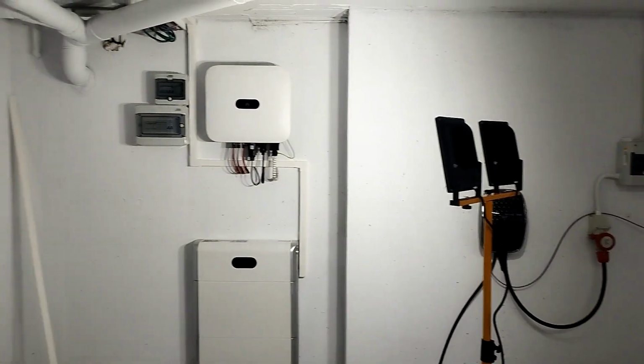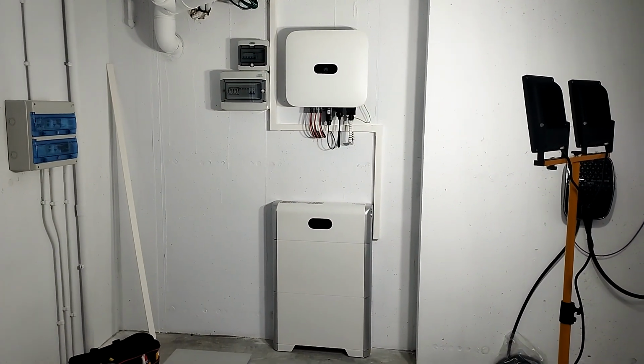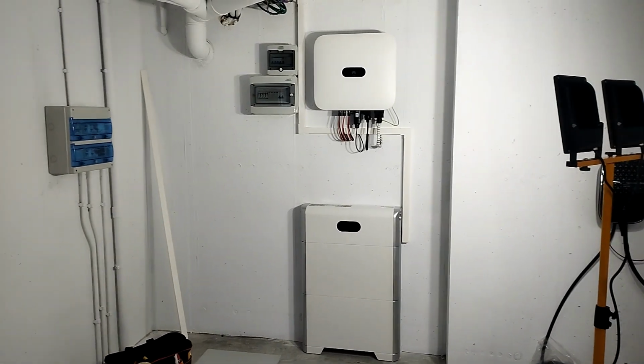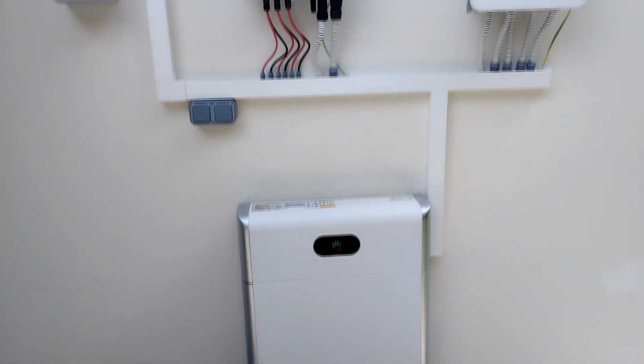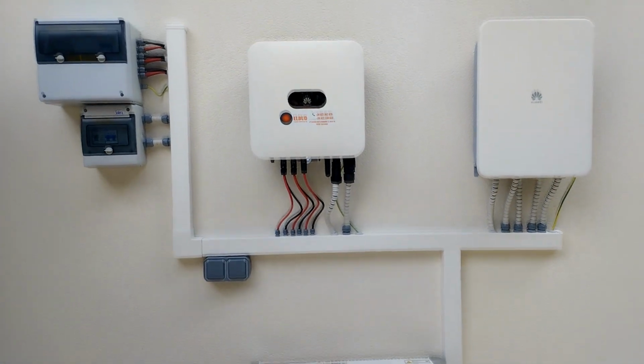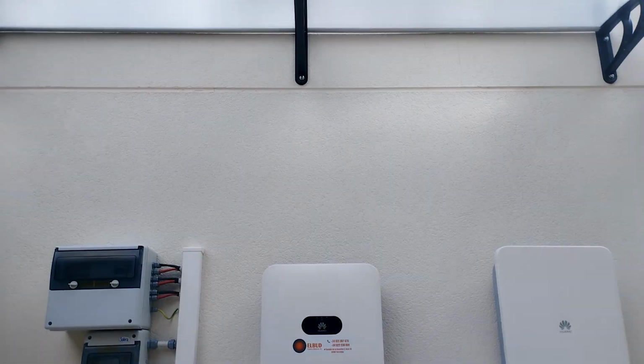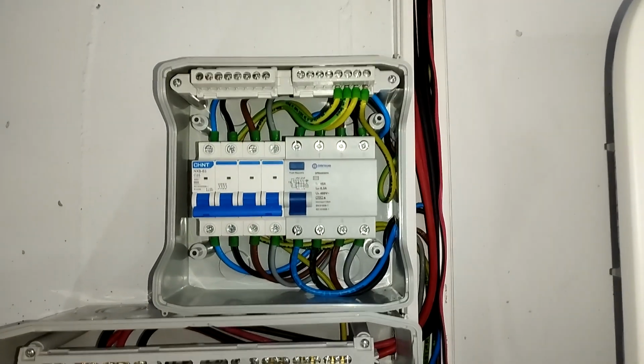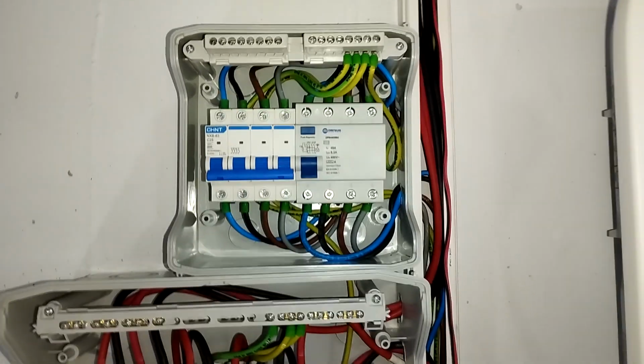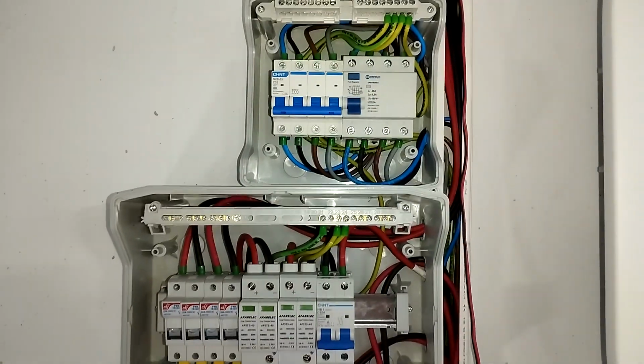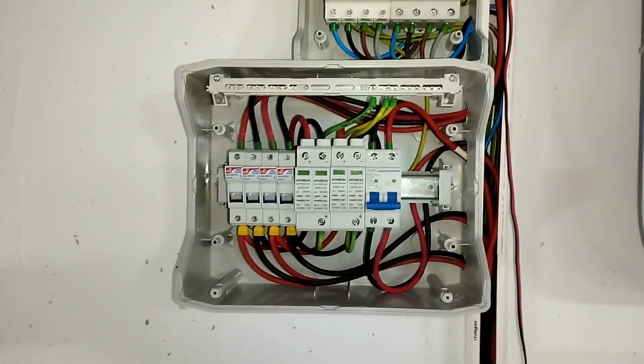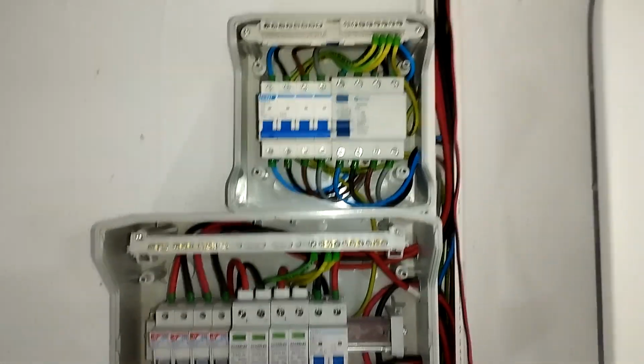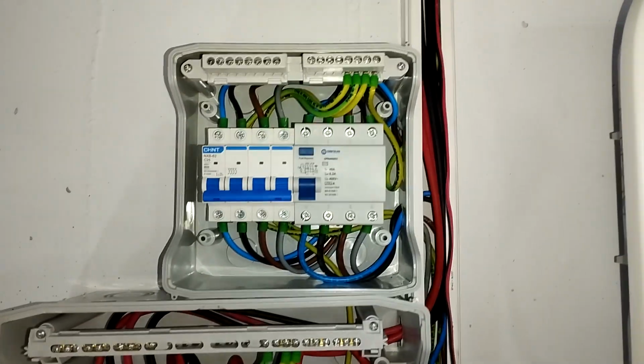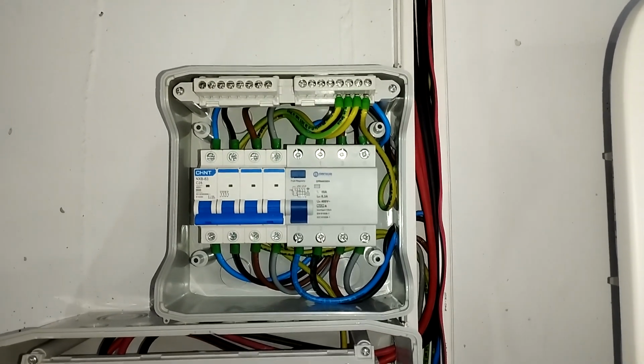In this project, we're installing the inverter in the basement, but it may also be installed outdoors. If installed outdoors, the manufacturer recommends placing it under a roof or fitting a protective canopy to shield it from direct sunlight and rain. The inverter, solar panels, and battery must be protected with appropriate protective devices. We use DC fuses, DC circuit breakers, AC circuit breakers, RCDs, residual current devices, and surge protection devices, SPDs.